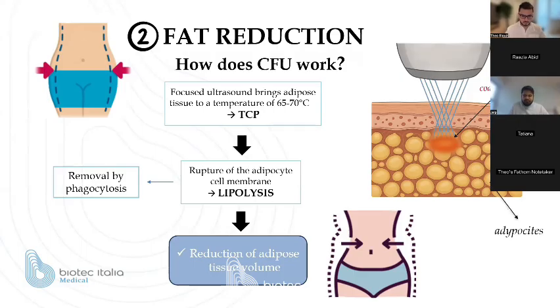Again, we are able to generate thermal coagulation points at a temperature of 65 to 70 degrees. These thermal coagulation points, which are generated in this case at the level of fat cells, adipocytes, rupture the membrane of the adipocytes. So all the content of the adipocytes is released outside into the interstitial fluid, and it is removed by phagocytosis, by our lymphatic system. This is basically the process. It is called lipolysis, and the result is a reduction of the volume of the adipose tissue.